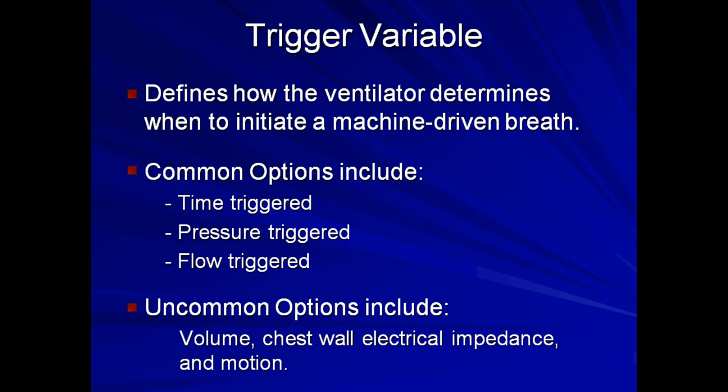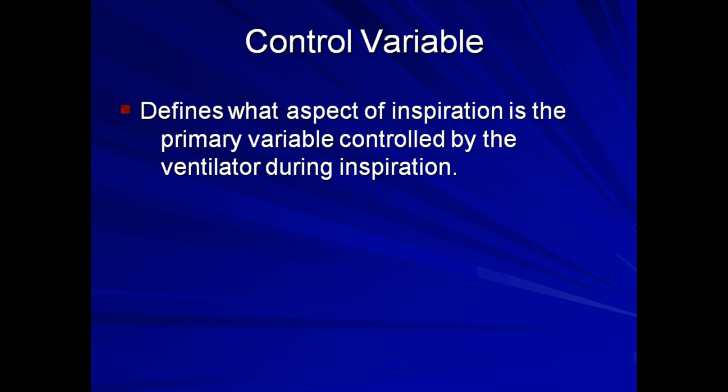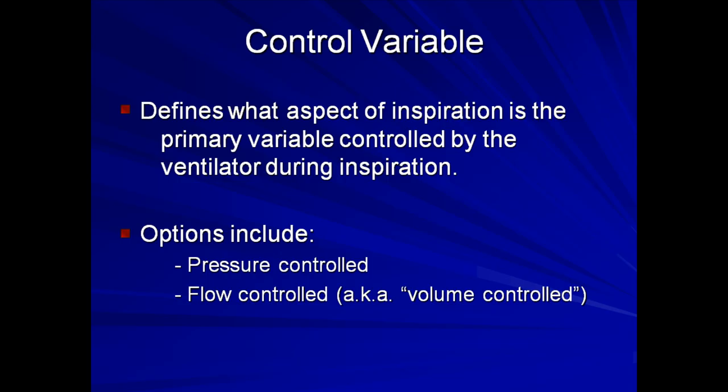The control variable defines what aspect of inspiration is the primary variable controlled by the ventilator during inspiration. The most common options include pressure controlled and flow controlled. In pressure controlled ventilation, the pressure delivered to the airway is constant regardless of airway resistance or compliance. Therefore, if pressure is preset and constant, changing resistance or compliance results in changing tidal volumes. In flow controlled ventilation, the flow is controlled as a function of the preset tidal volume and the additional designation of flow pattern. If flow is predetermined, changes in resistance or compliance result in changes in airway pressures.